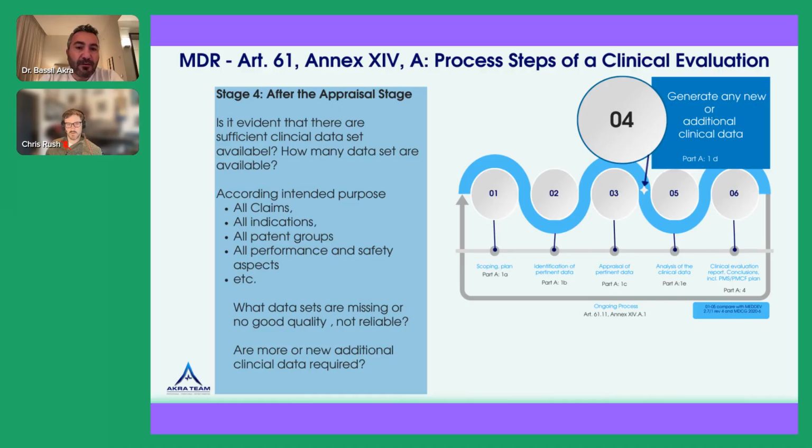The clinical evaluation process is a process which starts with a protocol, with a plan, at a very early stage, where you need to understand: what do I want to achieve? To be able to define how much data would be sufficient at the end, you need to understand your device, your intended purpose, your indication, your claims. And at the end, you will be questioned whether your data are sufficient based on the evidence that you can provide.